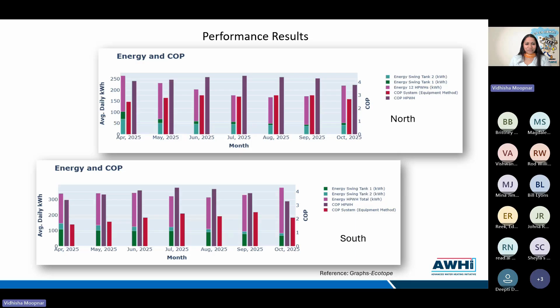One was following a qualified product list, so you're well aware of the benchmark of system performance needed, and also the swing tank set point. It was originally set at around 140 degrees Fahrenheit, which put a lot of dependency and pressure on the electric resistance water heaters. When that was reduced to around 130, system efficiency improved with major dependency on the domestic hot water.